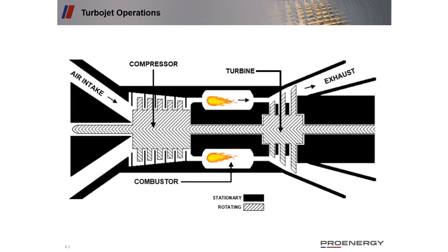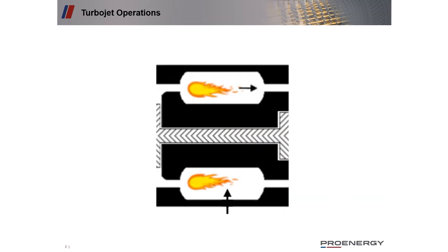In the previous episode, we discussed the LM6000 and major components. We discussed the operation of a general gas turbine, as shown here, and went through the overall operations at a high level. In this episode, we're going to go into the details associated with emissions of concern — how they're produced and ways to mitigate those emissions. We're going to talk about the combustor assembly and go over the PC versus PD, a water injection machine versus a dry low emissions or DLE type machine.